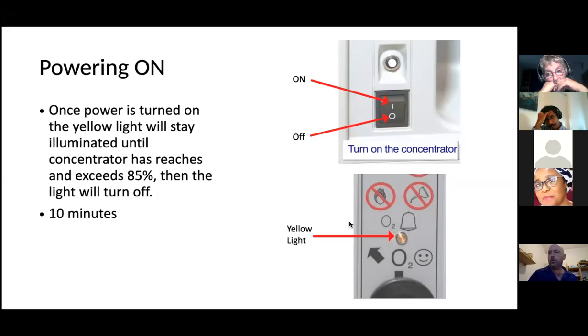If it takes too long, maybe we need to check if something is obstructing the inflow to the machine, or the room is not ventilated enough. I remember we had this problem in Kumasi South when we first installed them, because the room was not ventilated enough until there were air conditioners. The machine couldn't reach the oxygen concentration because there was not enough air in the room.